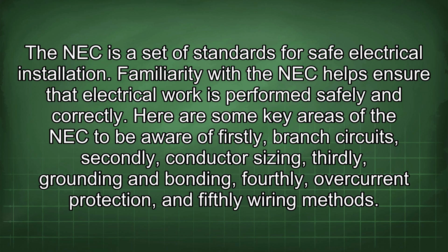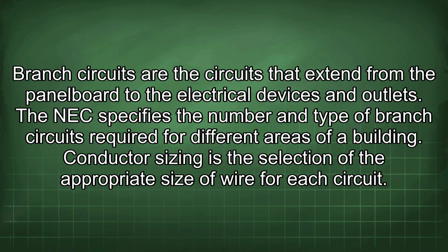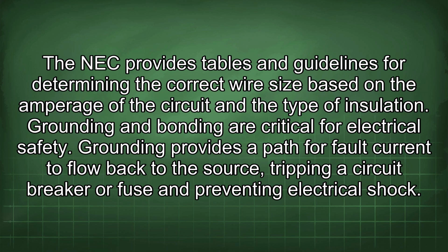And fifthly, wiring methods. Branch circuits are the circuits that extend from the panel board to the electrical devices and outlets. The NEC specifies the number and type of branch circuits required for different areas of a building. Conductor sizing is the selection of the appropriate size of wire for each circuit. The NEC provides tables and guidelines for determining the correct wire size based on the amperage of the circuit and the type of insulation.